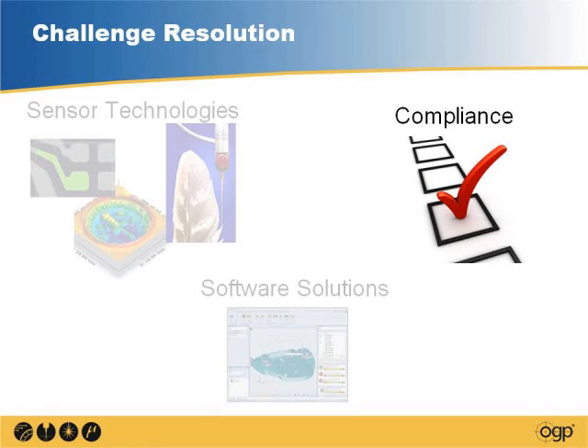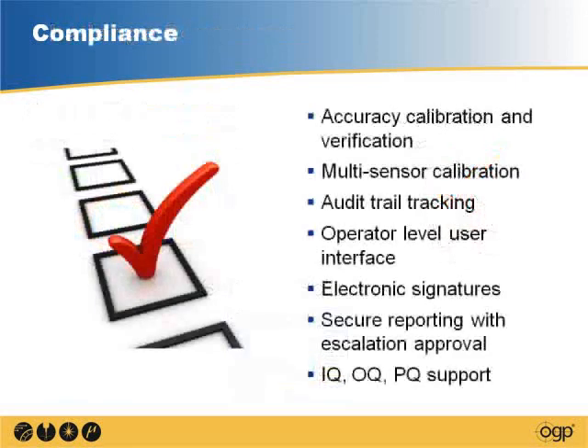When you're talking about a multi-sensing system, the calibration and the verification of the sensors to themselves and to each other is critically important as well. There are several patented techniques for understanding that and for really controlling that, which is something we've incorporated. Audit trail tracking, electronic signatures. If you are in an environment that's subject to FDA requirements, those kinds of things might be important to you.